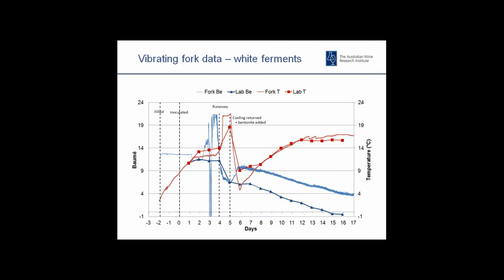So I'll just run through a series of graphs to show how the sensors actually performed during 2015. I'll start off with the vibrating fork. With all these graphs, we've got Baume down the left-hand side, we've got temperature on the right-hand side, and number of days of ferment across the bottom. So the Baume data is in blue, temperature data is in red. Now we had some issues with electrical signal here early on, and we also had an issue with cooling failure on one of the jackets.